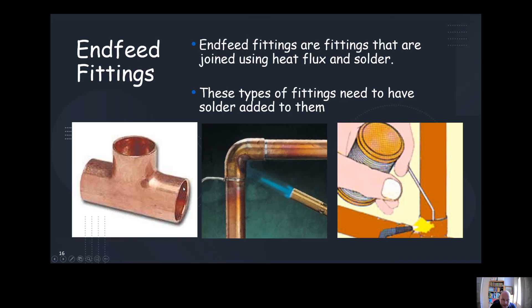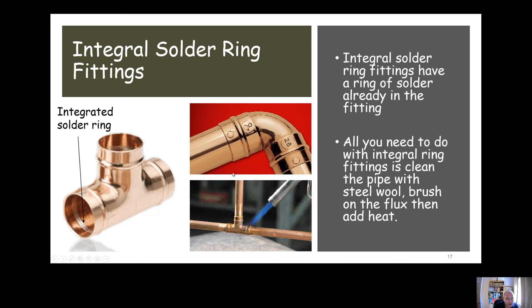End feed fittings are jointed using the process we've just looked at, but you'd need to add solder to them. Integral solder ring fittings, as you can see in the picture on the left hand side here, have a ring of solder integrated into them already. We can see with this raised bit here where the solder's been integrated. With integral solder ring fittings, you'd clean up the pipe, clean up the fitting, put the flux on, add heat, and then the solder would come out when it reaches the melting point.